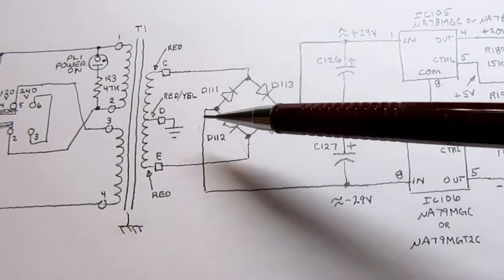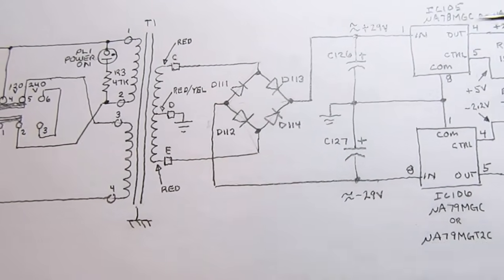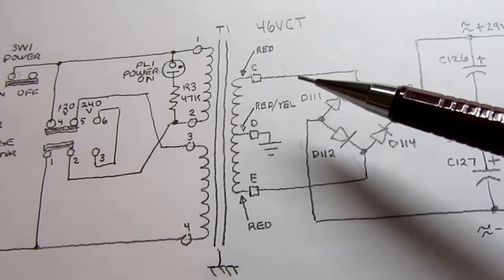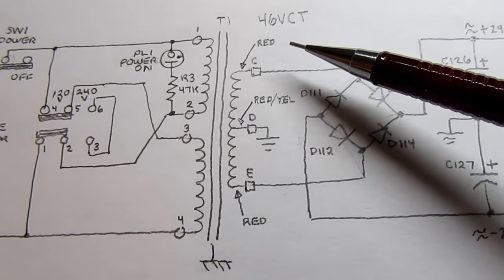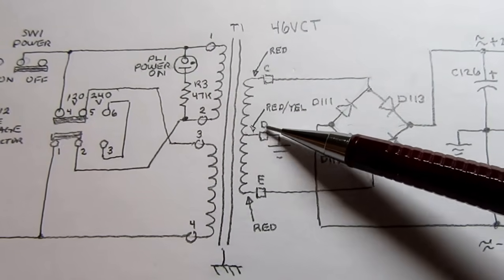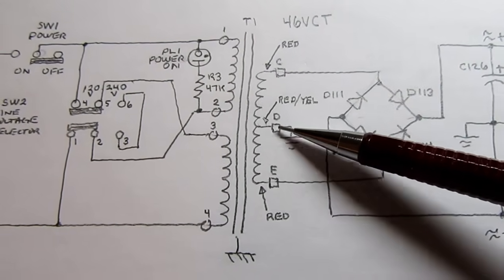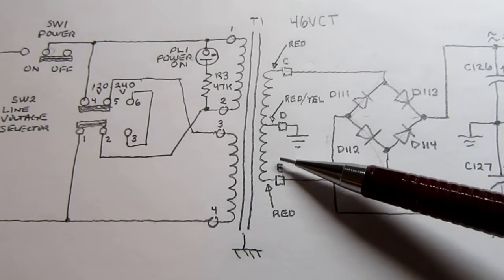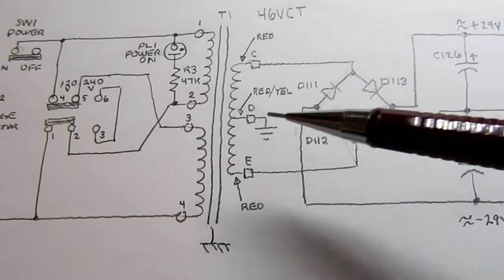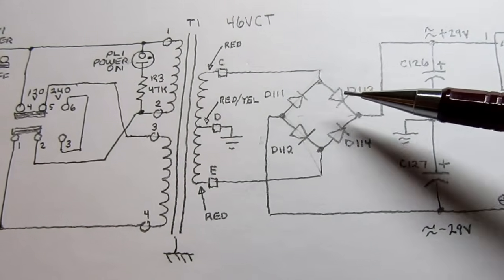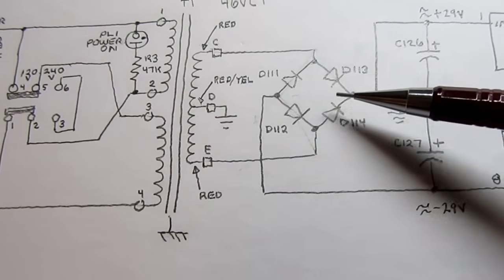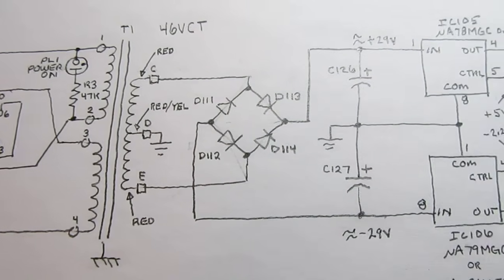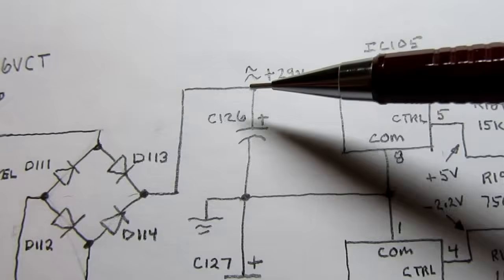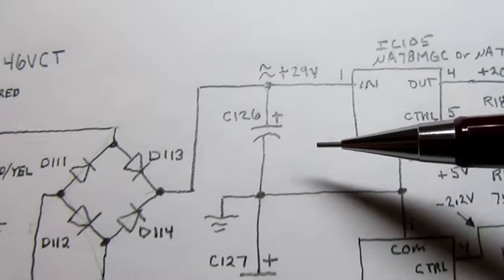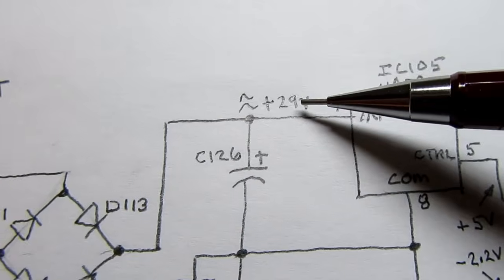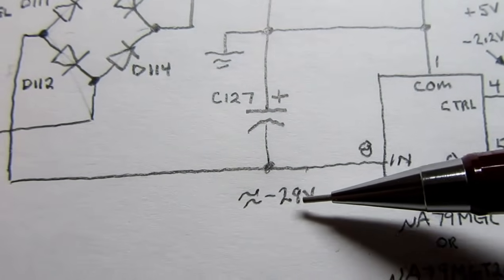The secondary is a standard center tap secondary. The secondary winding is 46 volts center tap approximately, so it's 23 volts from the center tap to here, 23 volts from the center tap to here, or about 46 volts from here to here. The center tap is grounded. You have a full wave bridge rectifier, so that gives you, with the filtering of these 2 capacitors, approximately 29 volts here and approximately minus 29 volts here.